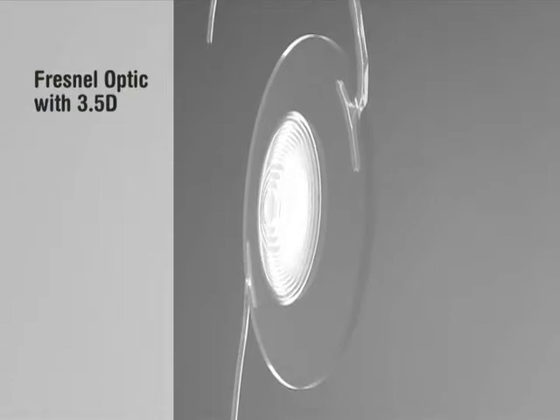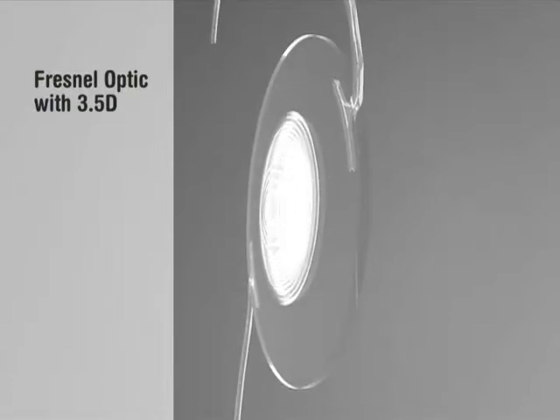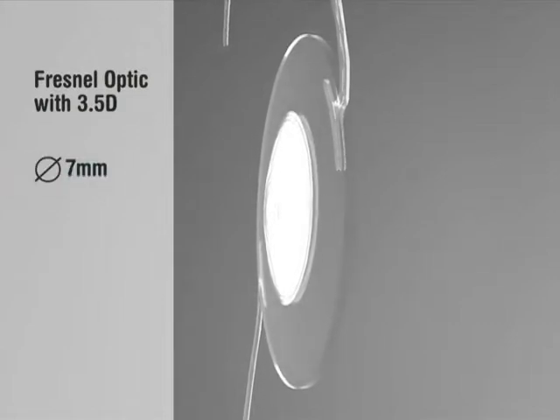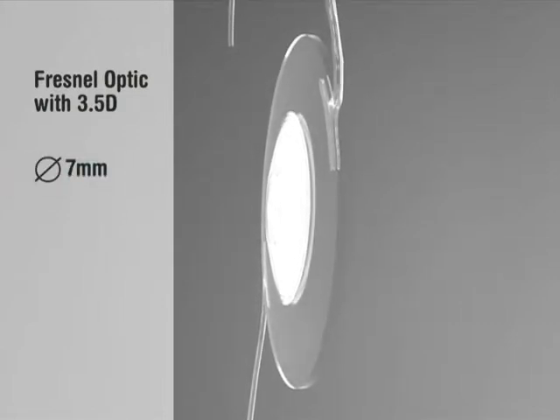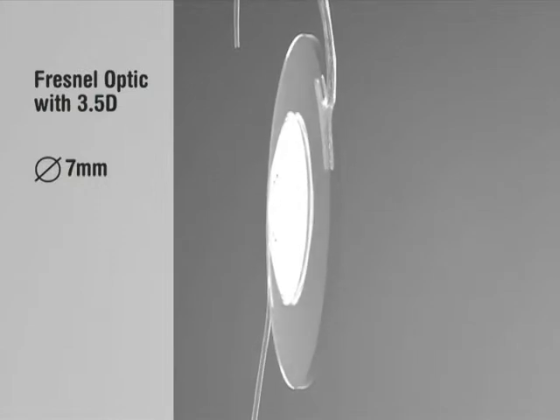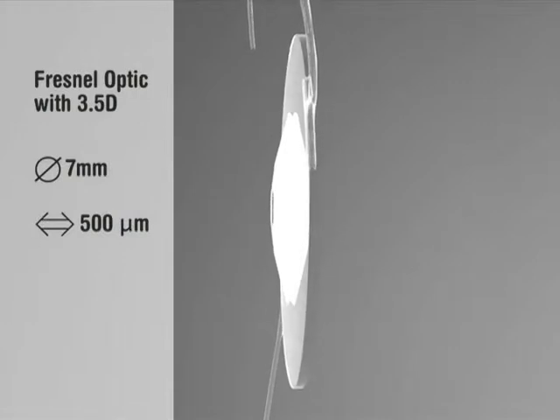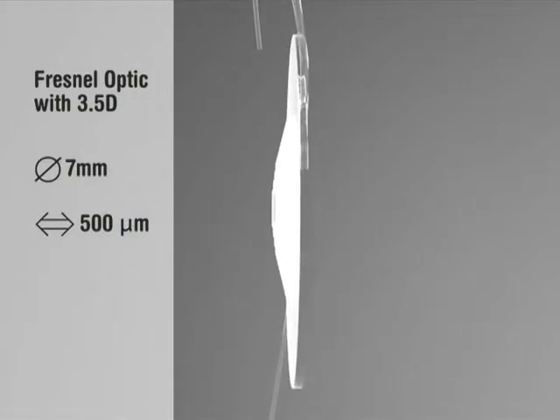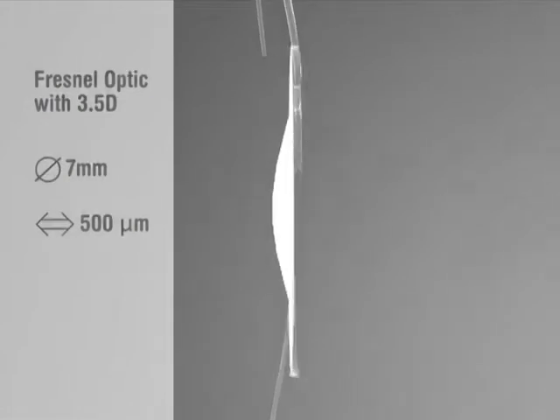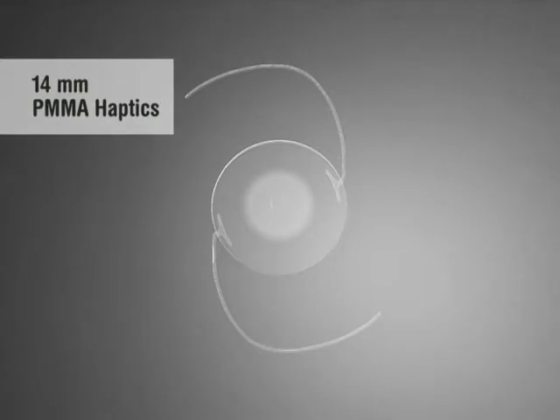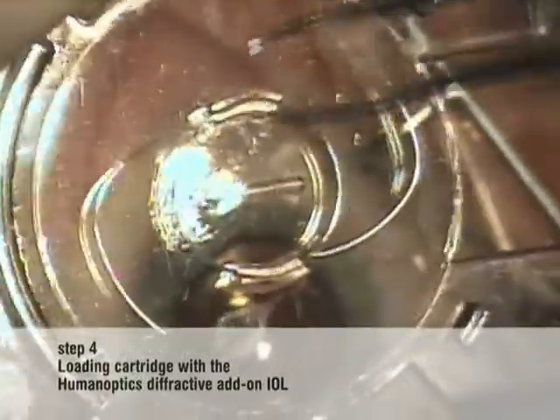This special add-on IOL does not behave like a capsular bag IOL placed in the sulcus by accident, but is specially designed for the sulcus. The 7 mm optic is big enough to prevent iris capture, and the silicone body is very thin — around 500 microns — and rounded to avoid any iris chafing or pigment dispersion. The 14 mm PMMA haptics fit into every sulcus and secure a perfect centration of the diffractive element.